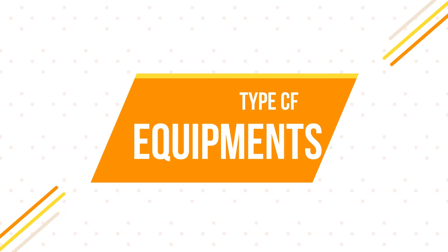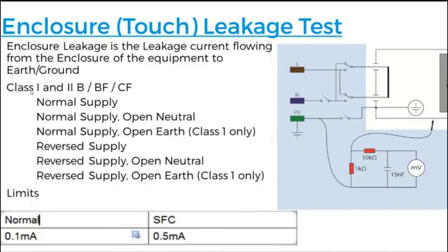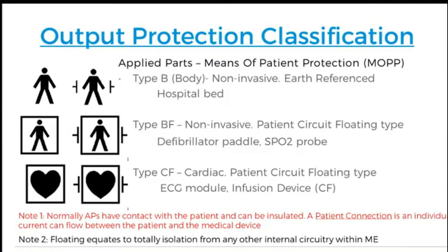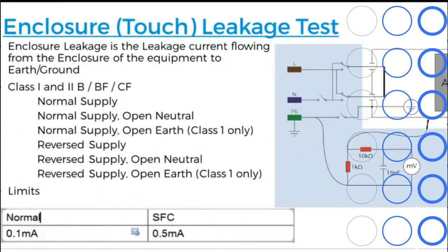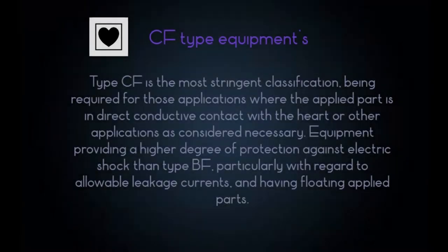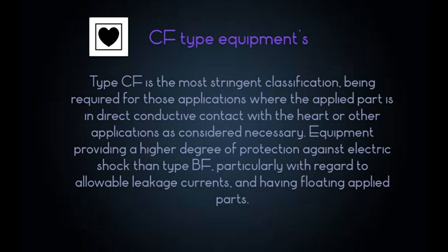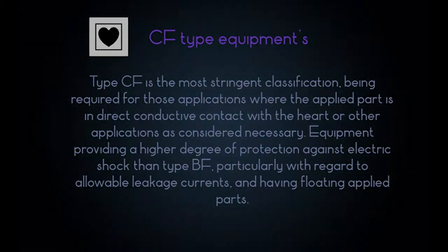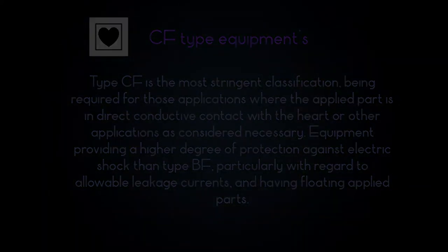The last type is CF Equipment. Type CF is the most stringent classification, being required for those applications where the applied part is in direct conductive contact with the heart or other applications as considered necessary. It provides a higher degree of protection against electric shock than Type BF, particularly with regard to allowable leakage currents and having floating applied parts.